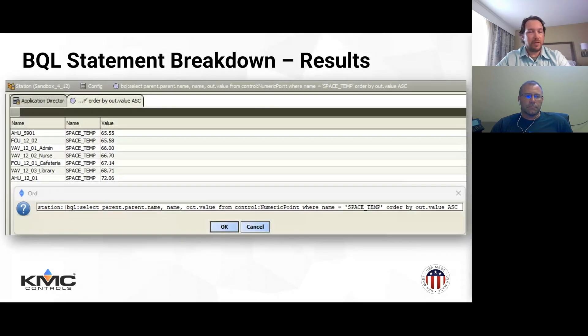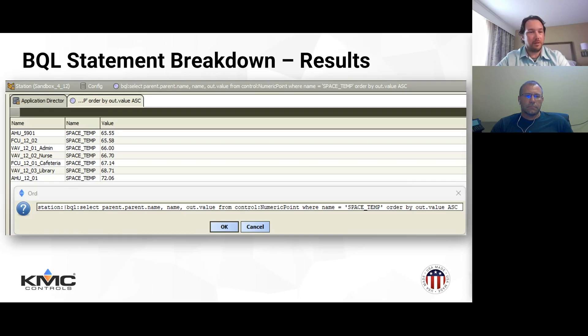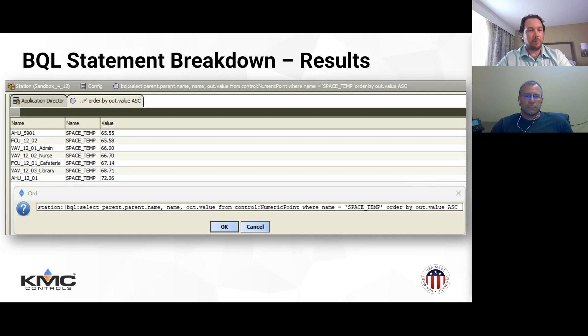Here is a result of that query we were building. We've got the device name, point name, and value of all the numeric points in MyStation that have the name 'space temp'. You can see the results were all sorted in ascending order - a quick way to grab table data, or if you're looking for alarms or temperatures over 80 degrees, things like that.